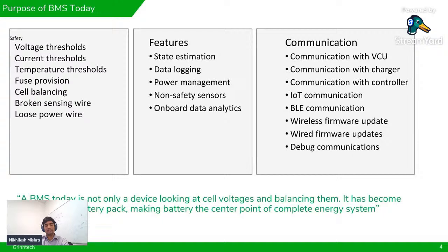Now let's say you cannot measure the cell voltage because the wire is broken, and you're reading the wrong voltage. It's possible, because when the cell sensing wire is broken, it can send you a floating voltage, and you might think the battery is still okay when it might not be, giving you a wrong reading. So present-generation BMS, especially good ones, will have a method of knowing if the cell voltage sensing wire itself is broken. It can do that.